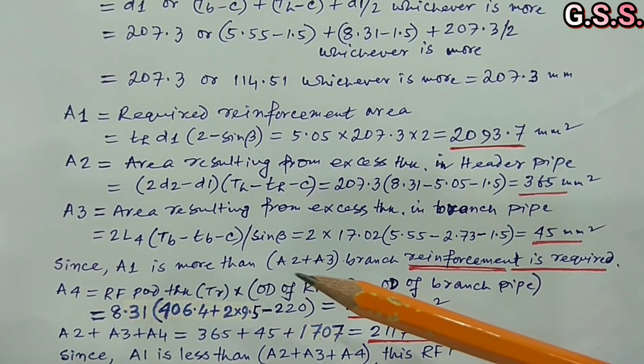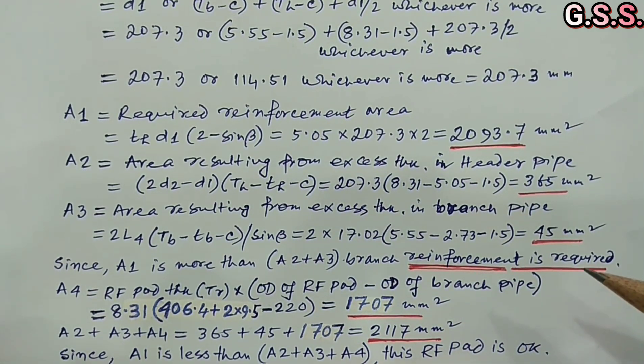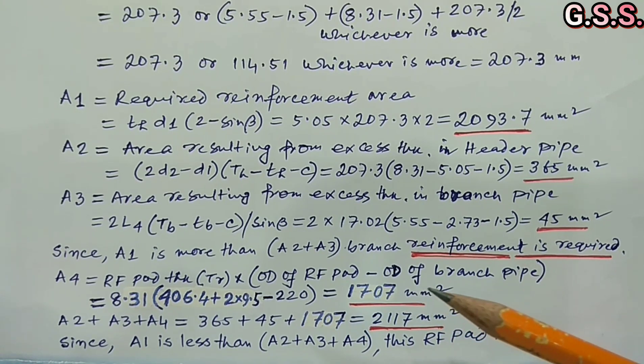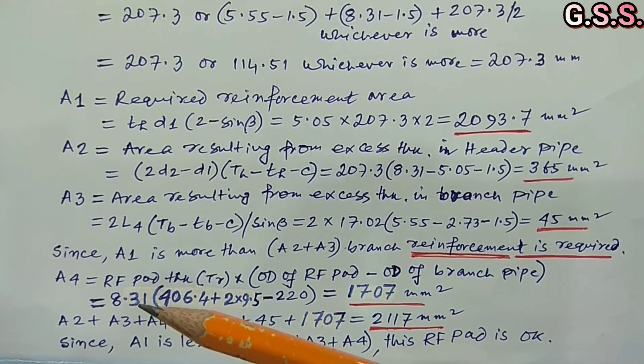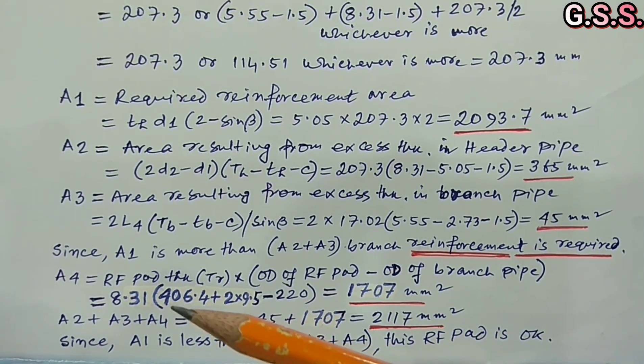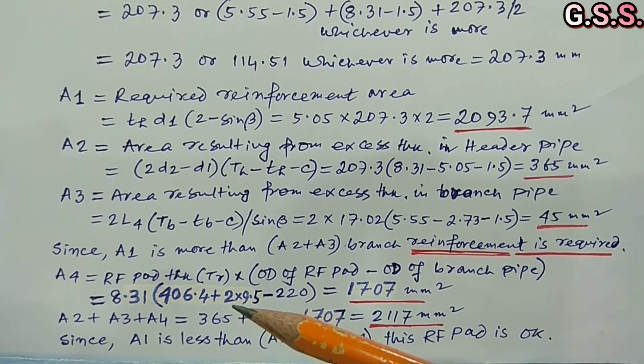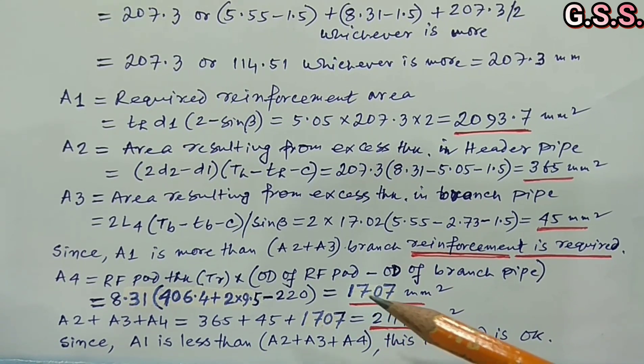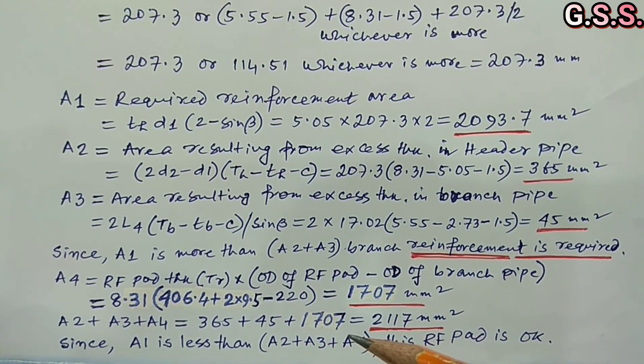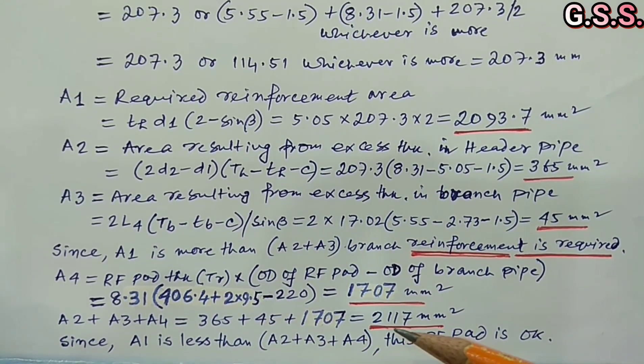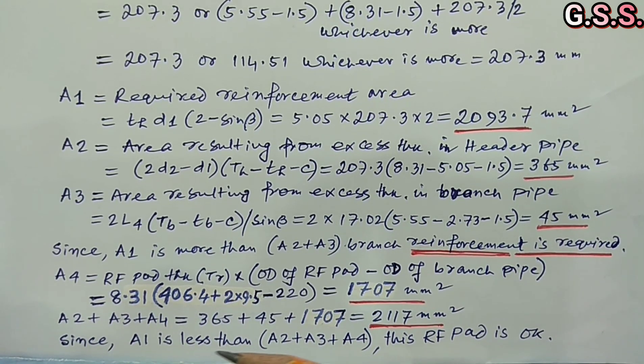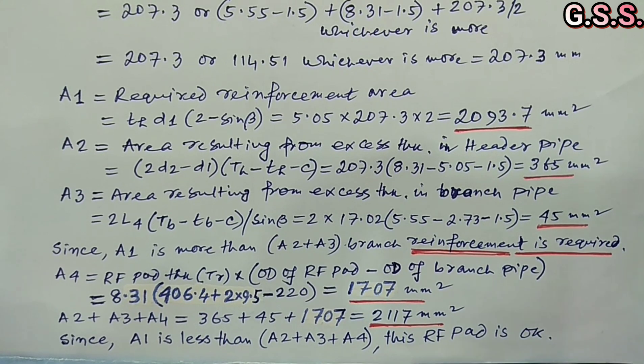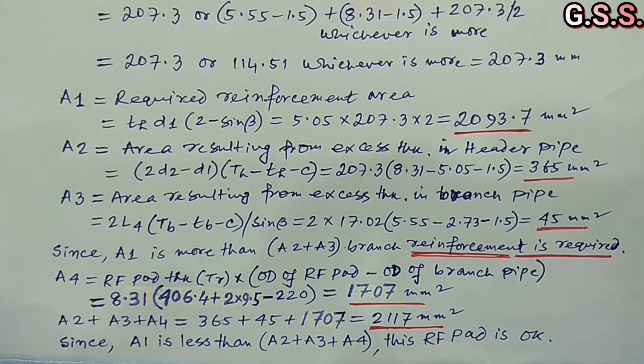Since A1 is more than A2 + A3, branch reinforcement is required. Capital A4 = RF pad area = capital TR × (OD of RF pad − OD of branch). Capital TR = 8.31 mm. OD of RF pad = OD of header pipe (406.4 mm) + 2 × RF pad thickness − 220 mm (OD of branch pipe), giving capital A4 = 1707 mm². Now A2 + A3 + A4 = 2117 mm². Since A1 is now less than A2 + A3 + A4, this RF pad is okay. In this way we can check whether the branch shall be a reinforced branch with RF pad or an unreinforced branch without RF pad.